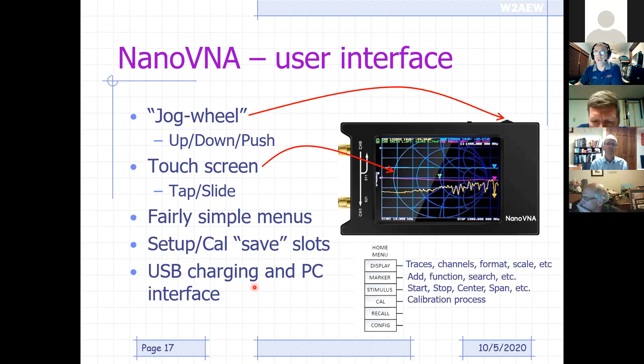So the calibration, one thing to remember is that most of the NanoVNAs only sweep 101 points over whatever frequency range you decide. So when you do a calibration, that means that your spacing for your calibrated points, if you will, is going to be equal to the frequency span divided by 101. And the VNAs will interpolate between those points if you set the span to a narrower range than what you calibrated. But it's always best, because you've got this relatively coarse spacing, to make the calibration over the specific frequency range you're measuring.